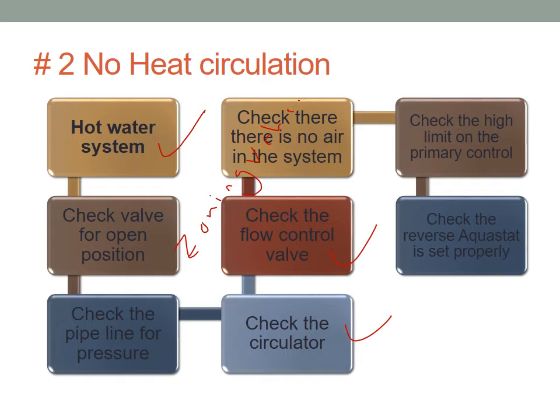There's always a purging valve near the boiler. Turn it on and let the water run a little bit so you get rid of air. This always happens whenever you change to new equipment or if you have a leak. A leak will cause you to have air in the system.